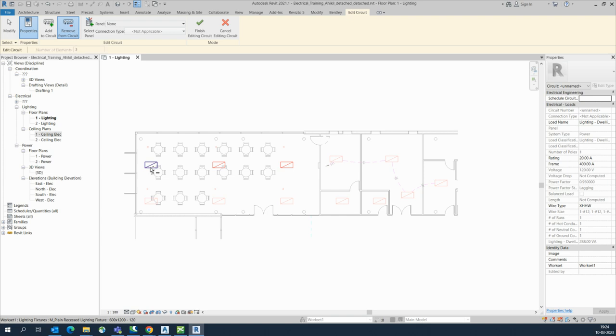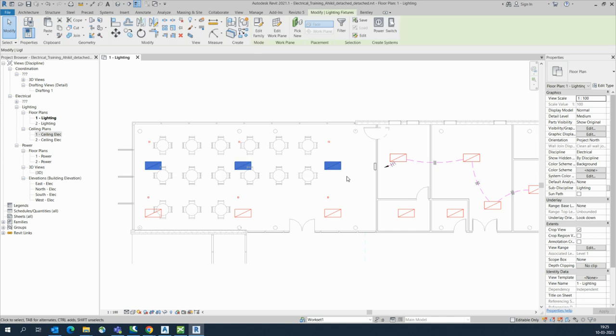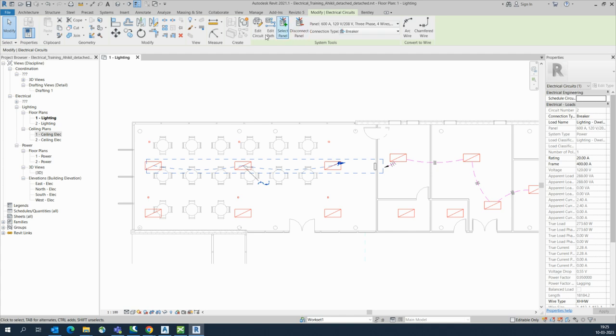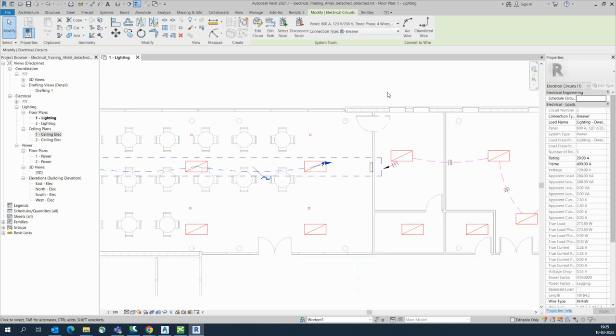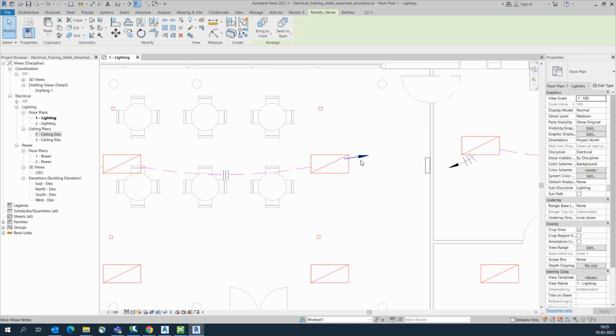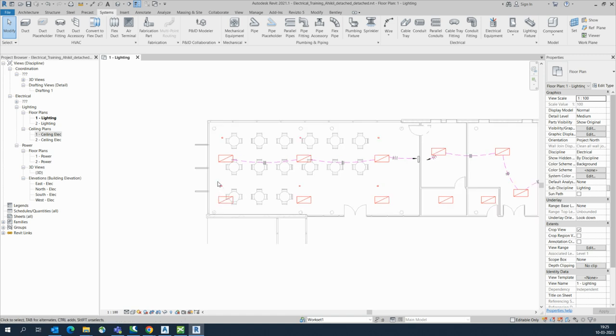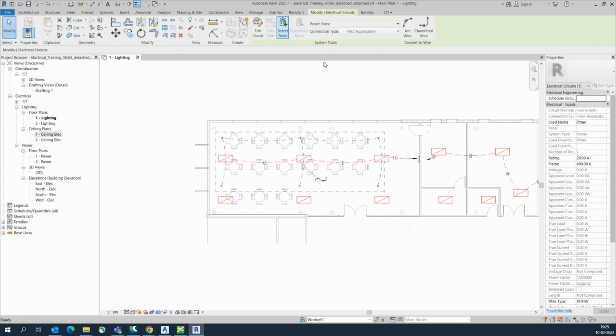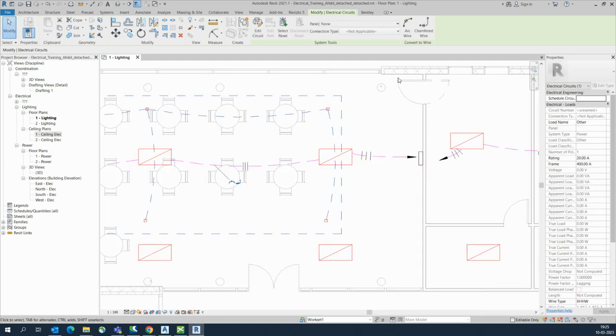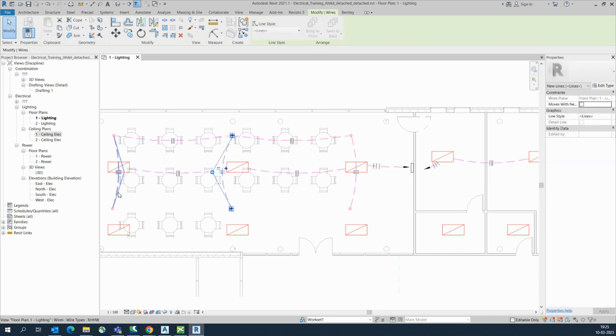Remove the lights from the incorrect circuit one by one. Once done, the system will show as unnamed. Select the lights again, give Power, select the correct panel, then choose Arc Wire. You can see the circuit now goes to the correct panel. Similarly, drag-select the remaining lights, give Power, select the panel, and add Arc Wire. Like that, you can easily give wiring to all the lighting.